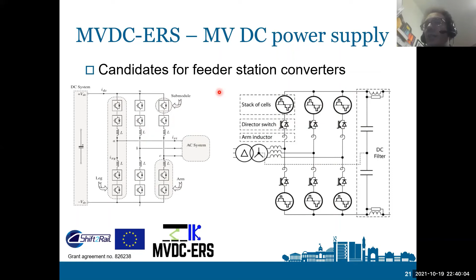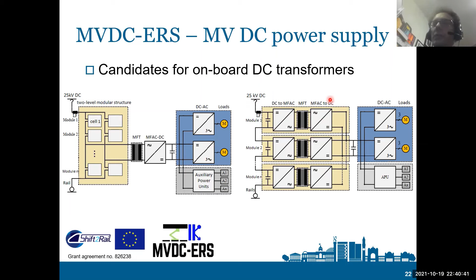Similarly, these are candidate topologies for the power electronics DC transformer, which are pretty much similar to the topologies already shown for the static frequency converter. The only difference is they operate as DC to AC and AC to DC using this medium frequency transformer. Fundamentally they have a series input and parallel output to step down the voltages.